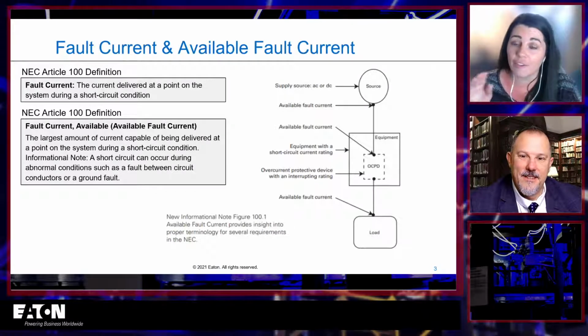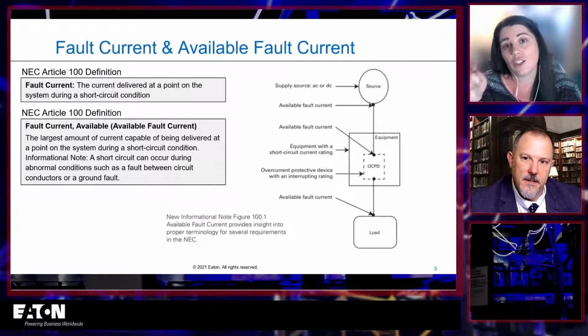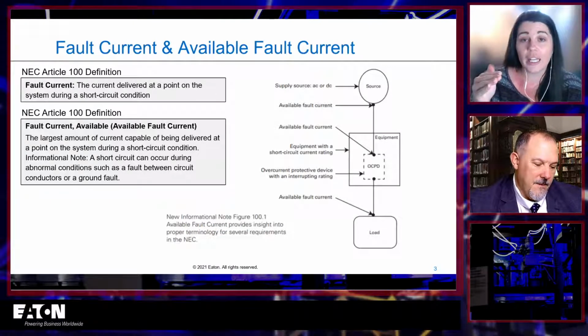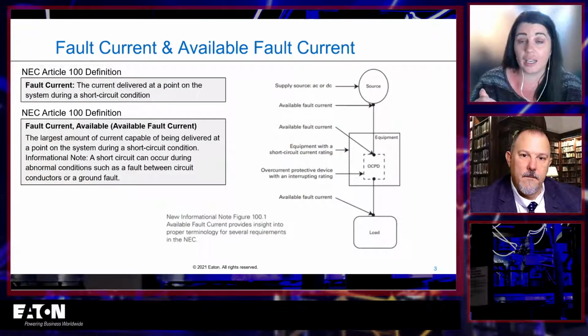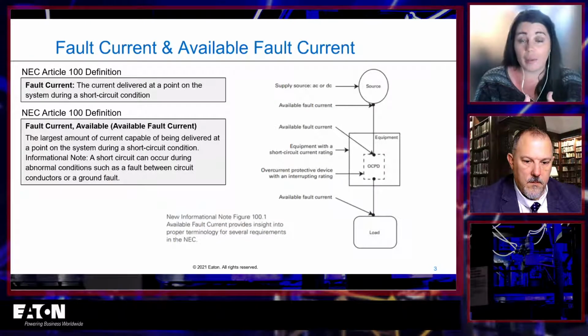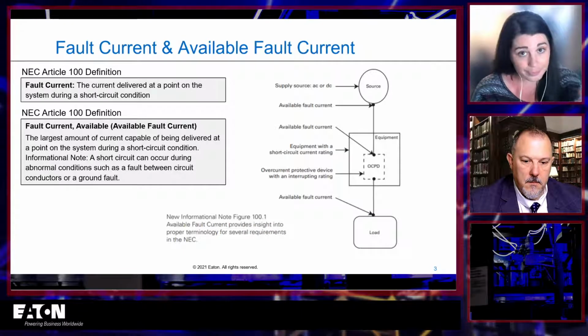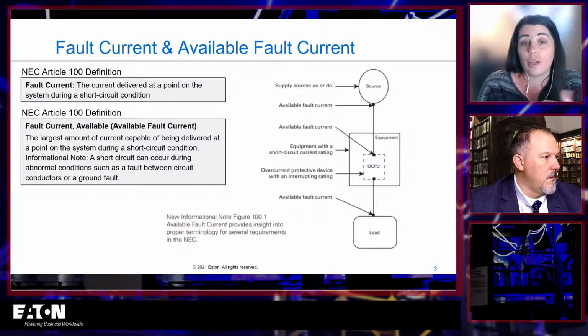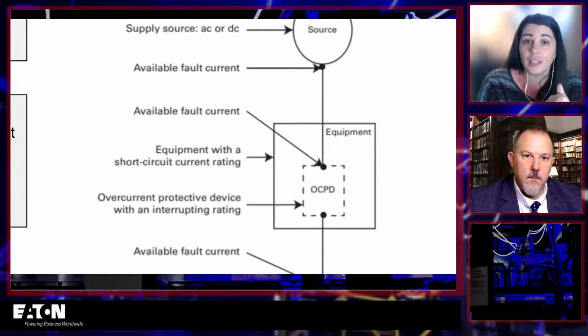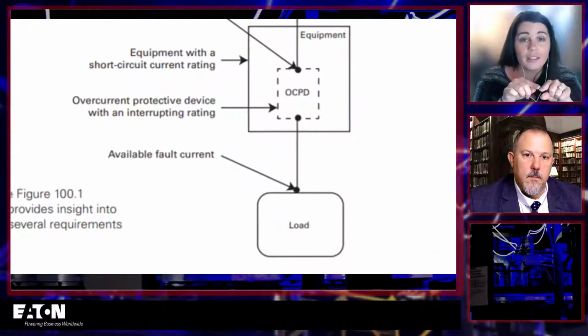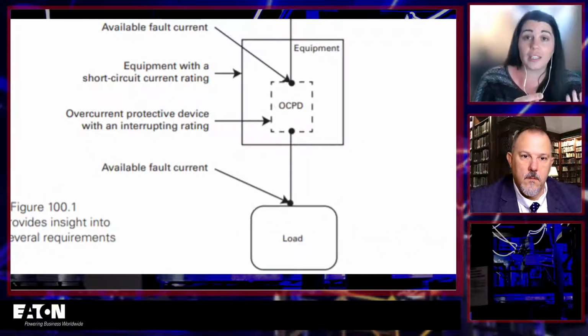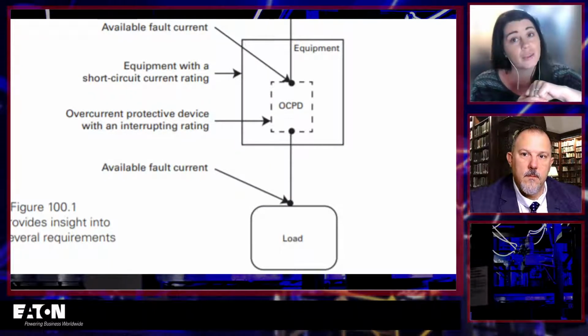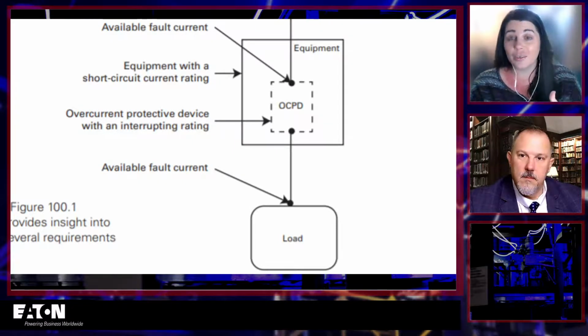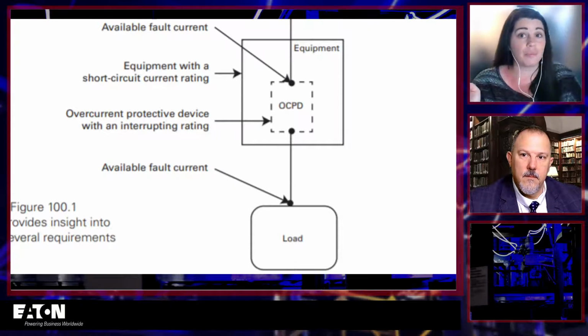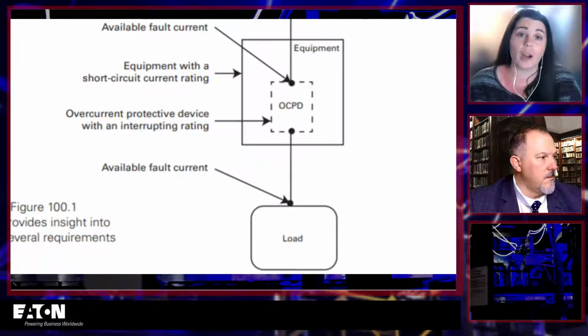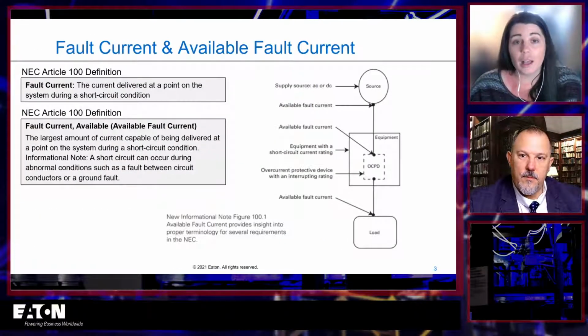And we have this nice little diagram. They added this informational note to the NEC as well. And what you can see is we've got a source. Right at the source, we have an available fault current. And then you can see we've got some sort of conductor, right? And there's going to be impedance in that conductor. So when that conductor comes into the incoming terminals of my next piece of equipment, it's going to have a different available fault current right there, to account for that impedance in that conductor. And then we've got that equipment right there. That equipment will have a short circuit current rating. It's going to have other devices inside of it, probably an overcurrent protective device with an interrupting rating. And then downstream from that to my next load, right? And that could be my final load, or it could be another piece of electrical equipment. It could just be a feeder going somewhere else. I'll have another available fault current because, again, more impedance in between.